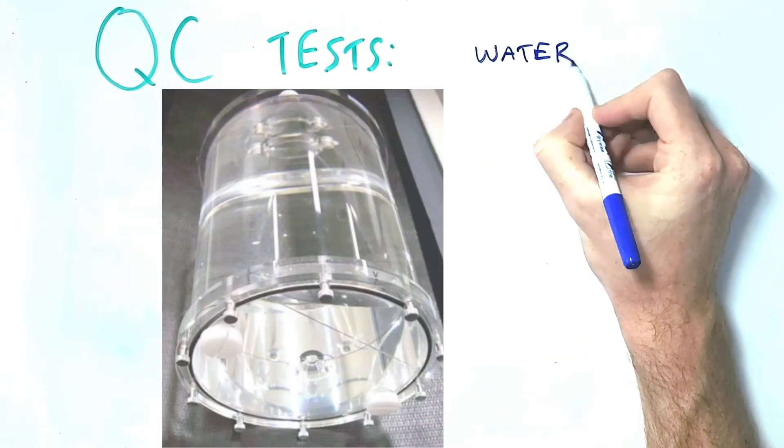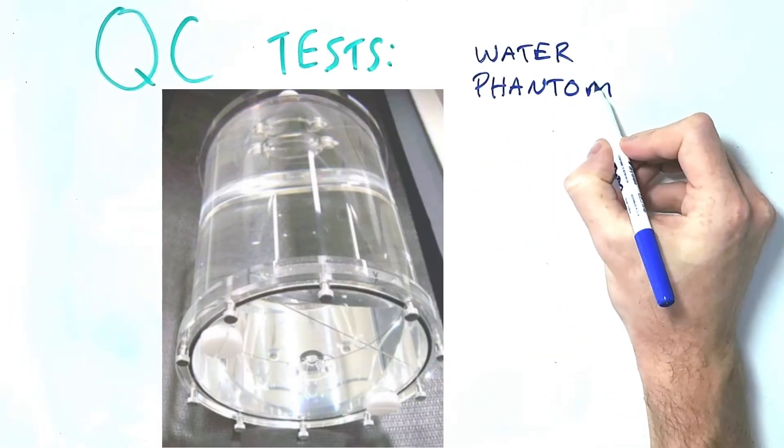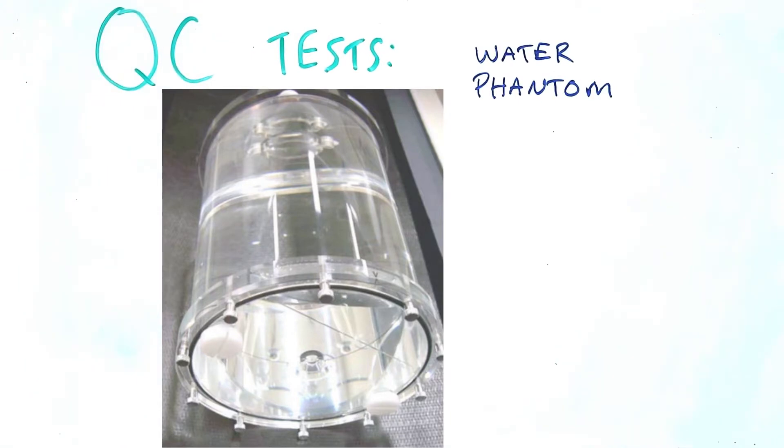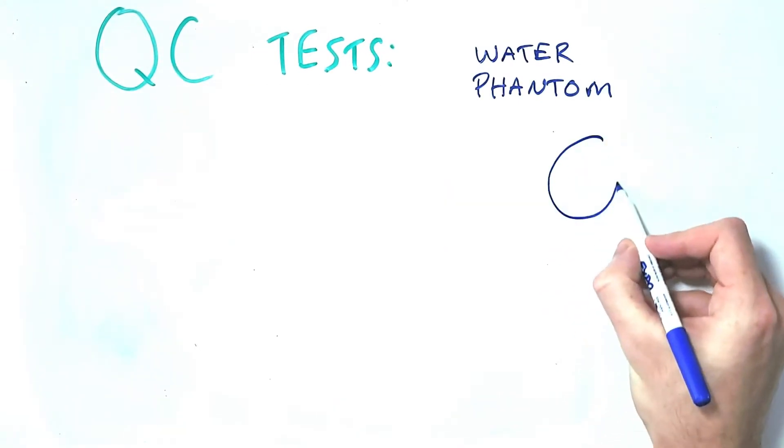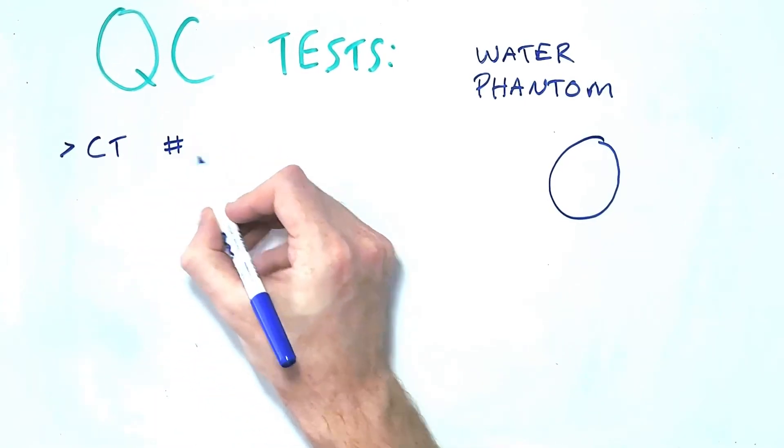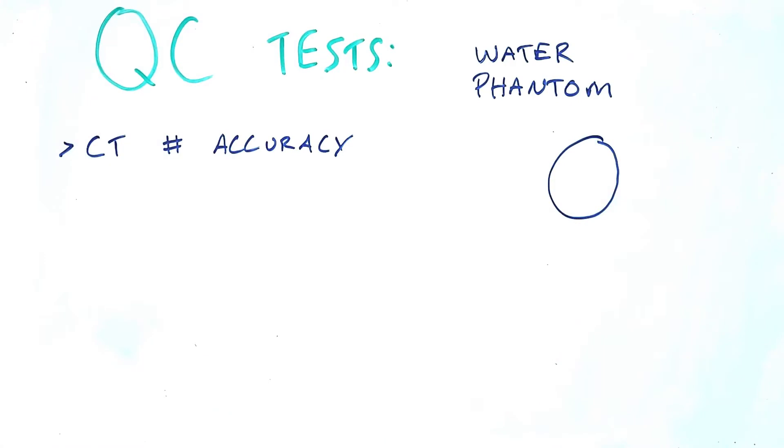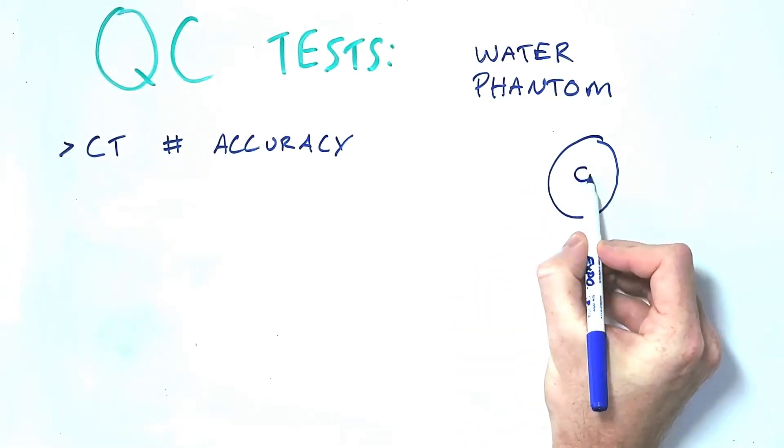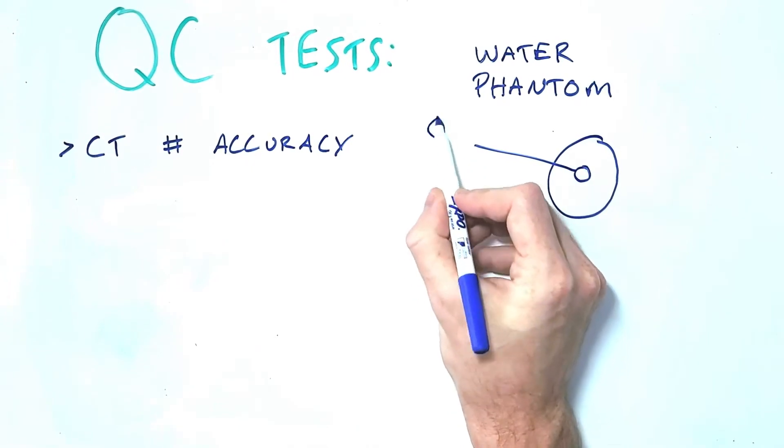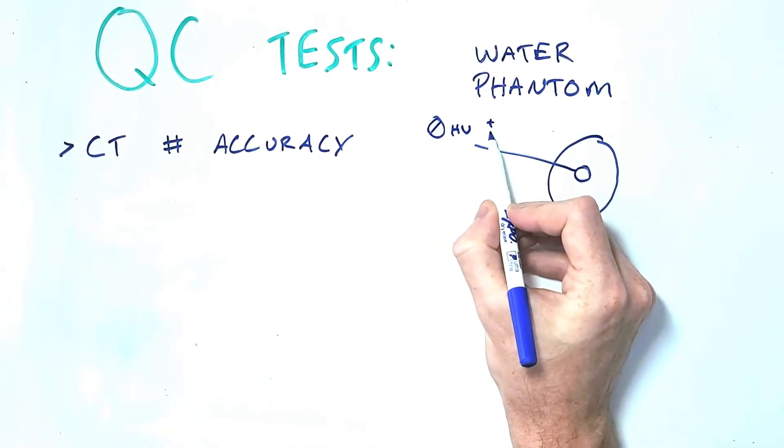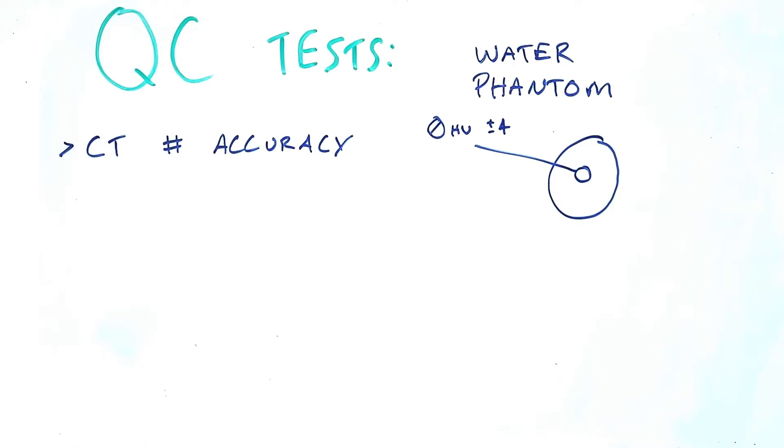Many QC tests are going to be performed with an acrylic phantom or a water phantom. As we know the CT number of water is 0 Hounsfield units so one of the most basic QC tests we'll do is to test the CT number accuracy by scanning the water phantom and assessing how close to 0 that number is in the middle of the phantom. The CT number for water should vary from 0 by no more than plus or minus 4 Hounsfield units.